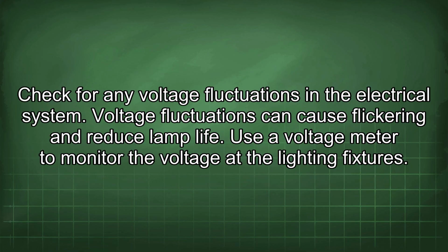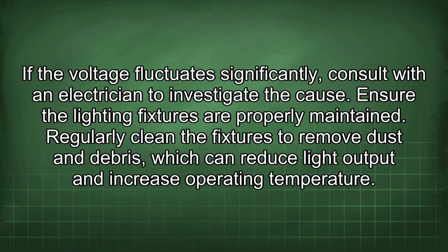Check for any voltage fluctuations in the electrical system. Voltage fluctuations can cause flickering and reduce lamp life. Use a voltage meter to monitor the voltage of the lighting fixtures. If the voltage fluctuates significantly, consult with an electrician to investigate the cause.